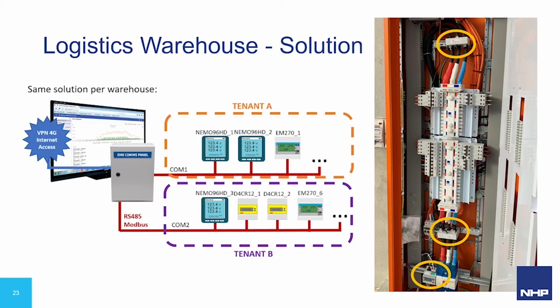So once the Smart eBOX and panel boards were manufactured and sent to site, the contractor installed them, wired them up, and then NHP came onto site to check that the meters were set up correctly with Modbus addressing and the like, to make sure all the data was being pulled correctly into the Smart eBOX.